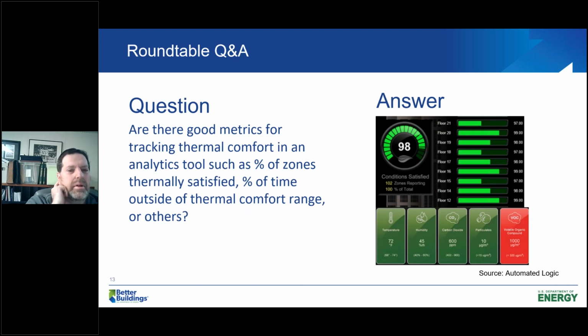Good metrics for tracking thermal comfort. You want to talk about some metrics, and I think you have a few examples here. Yes, thank you. There are a couple of examples here on the right. This is actually from one of the BAS providers, Automated Logic, and EMIS providers have this as well. The main things people are looking at are creating reports from different types of IEQ. If you look at the bottom right, it's maybe a little hard to see, but temperature is very typical in zones. This is reading 72 degrees, and there's a range of 66 to 74 degrees here. So how many zones are within that range and how many are out of it, to give it an overall score. And the same thing with relative humidity, if you have RH sensors that you can monitor.